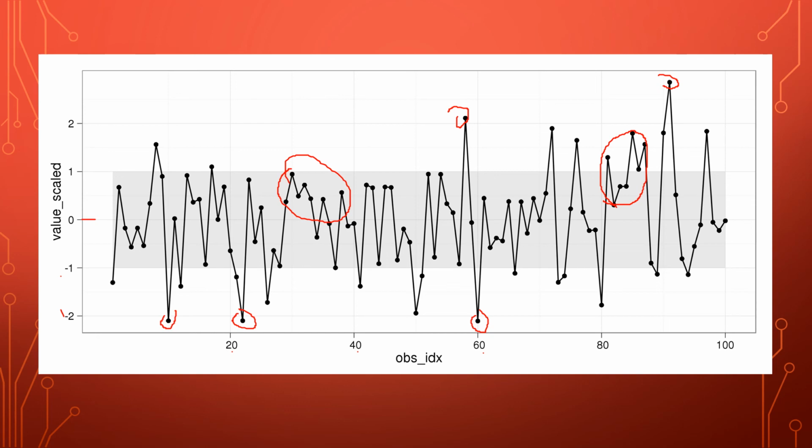All on the same side of the mean. Why are there so many on the same side of the mean? We don't like to see that. You have 1, 2, 3, 4, 5 runs all on the same side of the mean. We need to check our reagents and make sure that they're within date, not deteriorated, and stored properly.